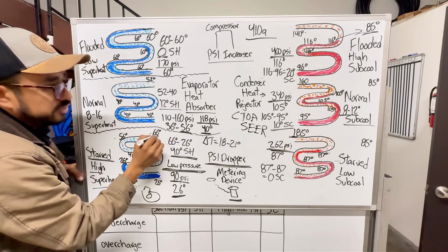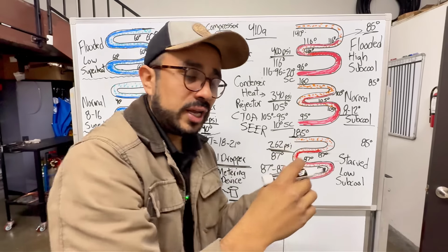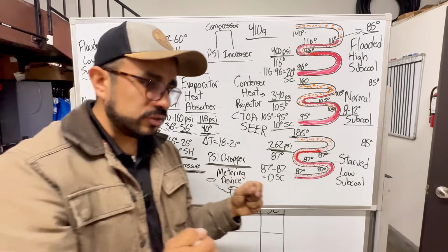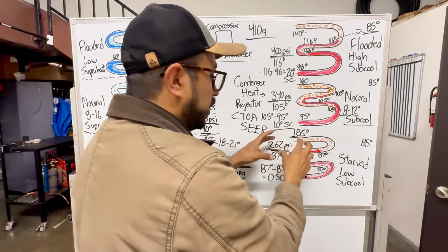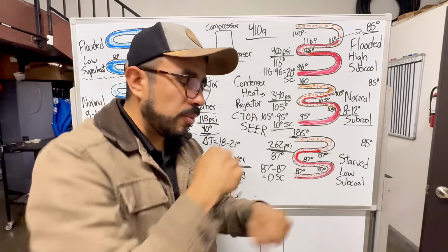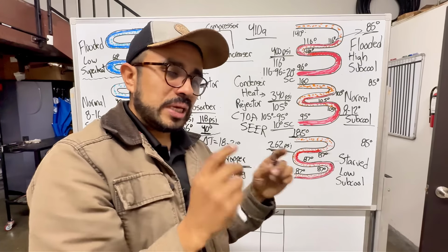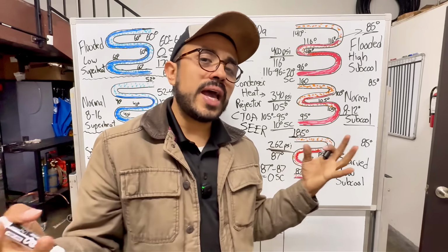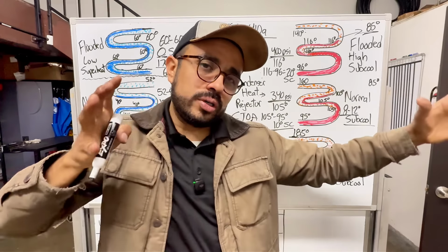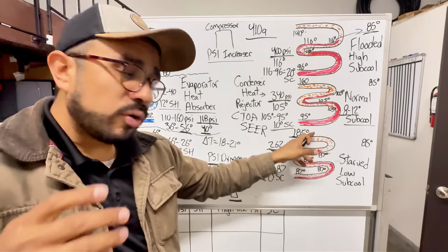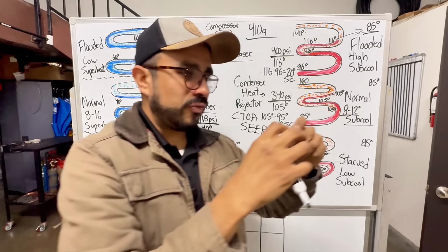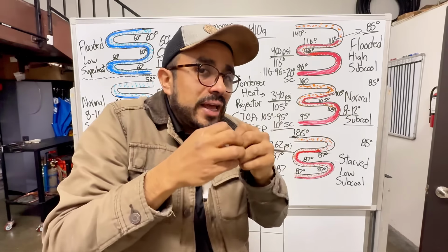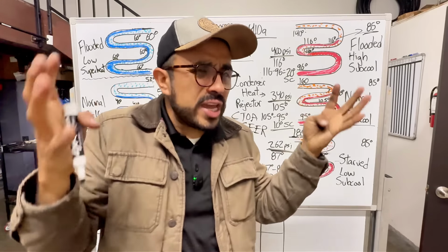Because it's higher, 66, your discharge line temperature is going to be a lot higher. And there's something called volumetric efficiency. The refrigerant coming on this side, you want the compressor to compress a good vapor temperature, but the hotter that vapor temperature is, the less weight it has, and you're just expanding it more, and you're going to end up with not only a higher discharge line temperature, but your vapor molecules are going to be more expanded.